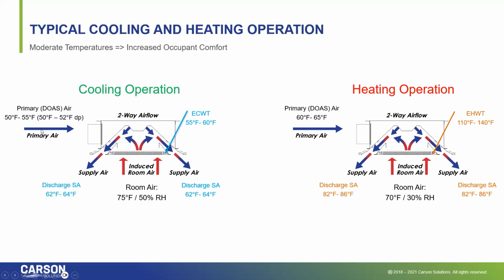And you have primary air, 100% outside air, being delivered to this plenum. In cooling, that outside air is somewhere between 50 and 55 degrees, and in heating, it's somewhere between 60 and 65 degrees. And as that plenum gets pressurized up to about a half an inch of pressure, it causes air to go out a series of nozzles, which creates a Venturi effect, which is a low pressure environment that pulls in, or induces, room air across a hydronic coil.